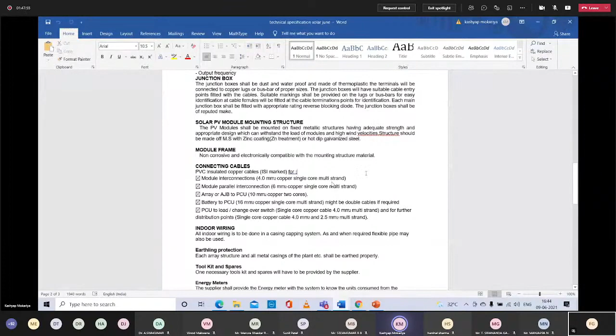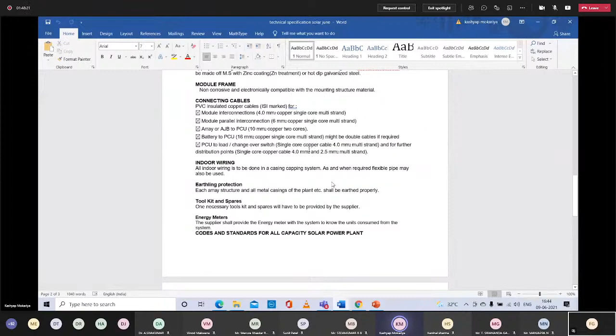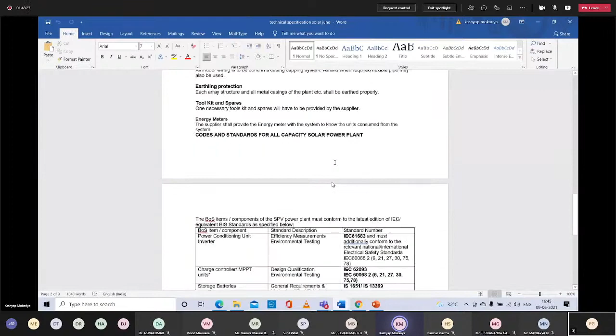I also have to show the cable sizes. When I draw the layout of the plant, I come to know the module interconnection, module parallel interconnection, battery to PCU, and PCU to load cabling, and which type of cable I'm using there, whether it's a multi-strand cable. I have a cable table along with design calculations, and by comparing both methods I finalize exactly what cables will be used, for the specification.